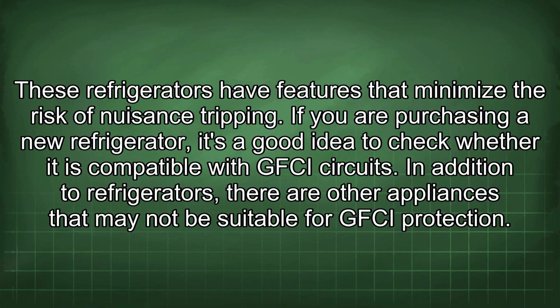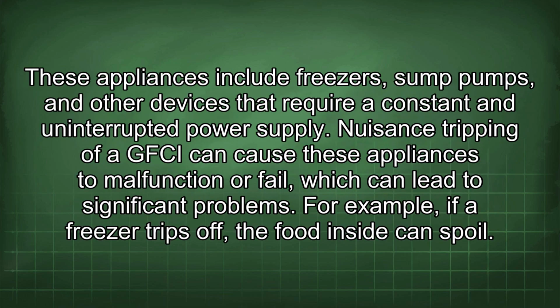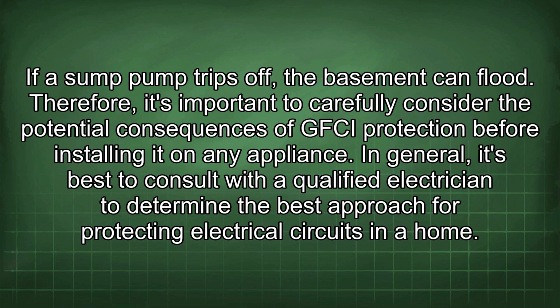In addition to refrigerators, there are other appliances that may not be suitable for GFCI protection. These appliances include freezers, sump pumps, and other devices that require a constant and uninterrupted power supply. Nuisance tripping of a GFCI can cause these appliances to malfunction or fail, which can lead to significant problems. For example, if a freezer trips off, the food inside can spoil. If a sump pump trips off, the basement can flood. Therefore, it's important to carefully consider the potential consequences of GFCI protection before installing it on any appliance.